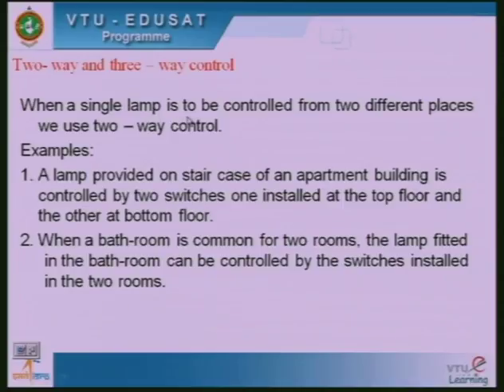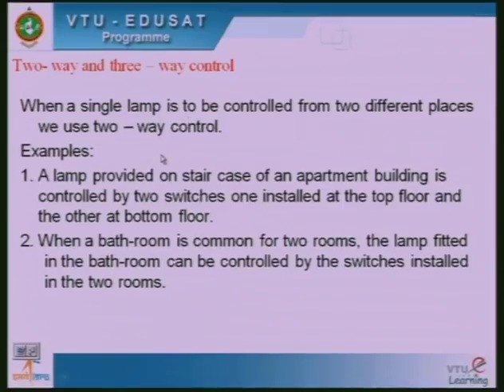See, when a single lamp is to be controlled from two different places, we use two-way control. I just gave two examples here. A lamp provided on the staircase of an apartment building is controlled by two switches, one installed at the top floor and the other at the bottom floor, okay. It is not necessary that it has to be used only in a staircase. The second example I have given is a single bathroom common to two rooms in a house, okay. I can control the lamp in the bathroom either from the first room or from the second room. So this is what you can have.